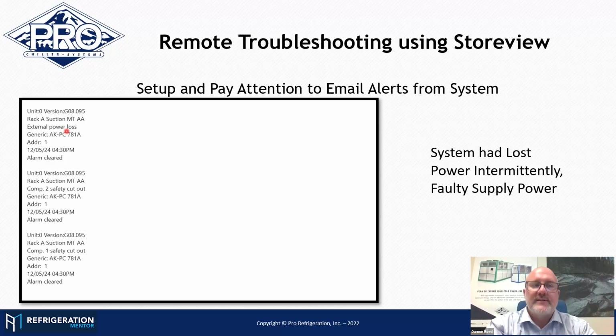So eventually what was identified here was the on-site power had issues. It wasn't creating any trips on any other equipment, but the chiller equipment was picking it up and saying, hey, we're not going to operate right now. So it went back to a utility connection issue. So yeah, all from an email.